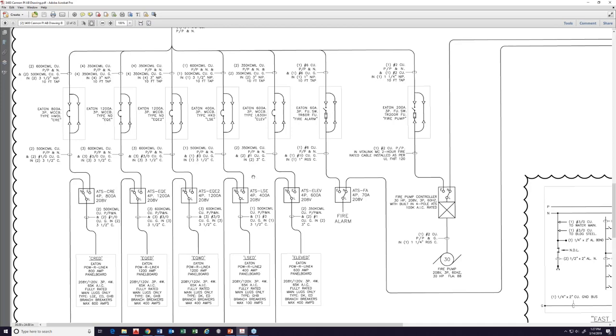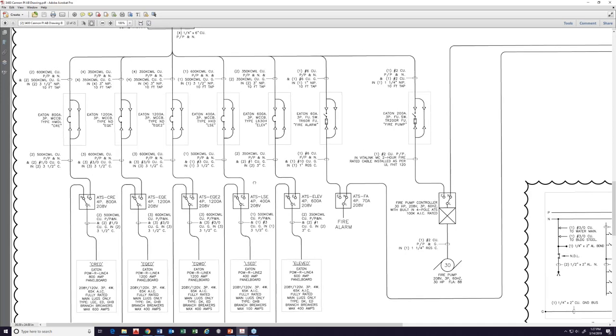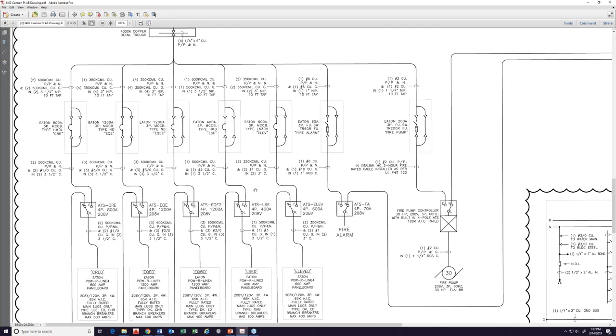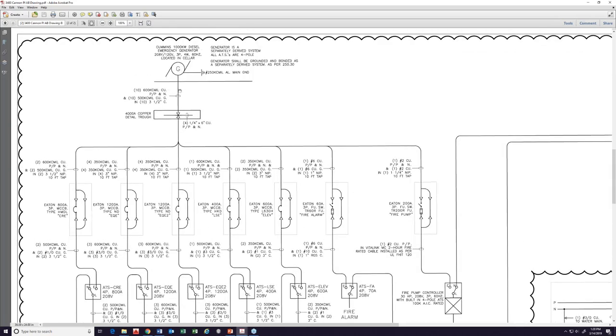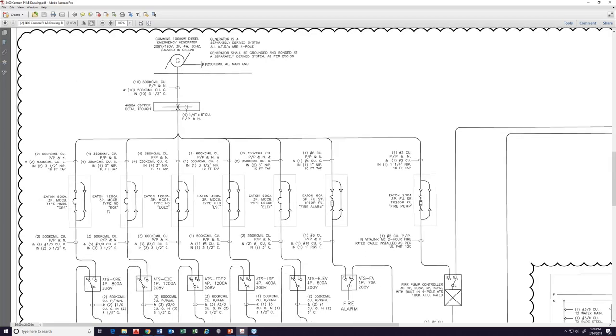Now, from an arc flash perspective, of course, it's also very safe, because we're not sizing very large devices. The arc flash hazard at the generator is going to be as big as the generator can produce. But these generators have protection packages built in, and if something goes wrong, it'll shut itself down. These, of course, are kept very short runs. These disconnects are very close to the generator, typically, either right next to it or in the next room or right above it or right below it. So the arc flash hazard is not going to be too great. And once I have these devices, it's not going to be bad at all.